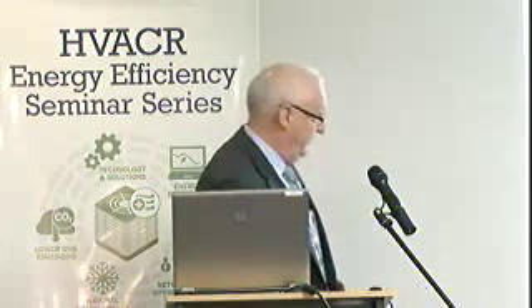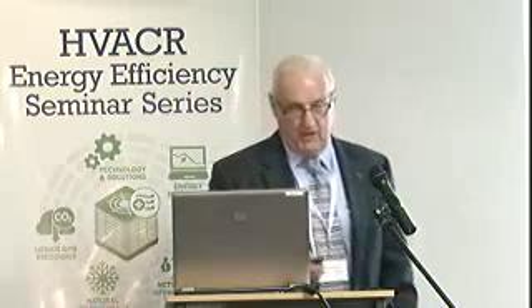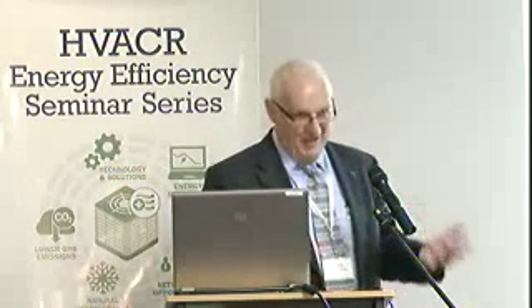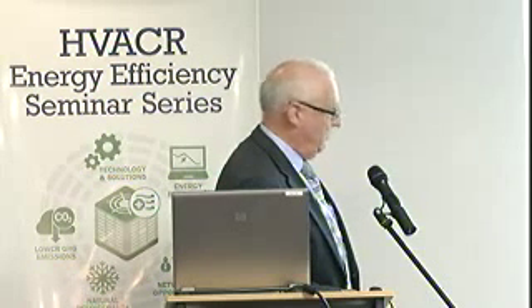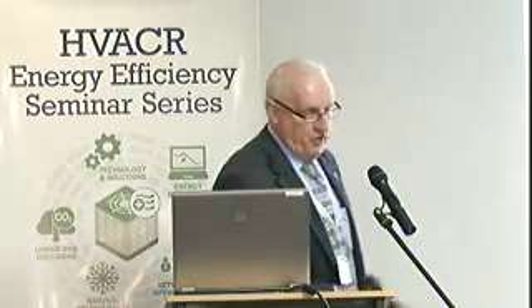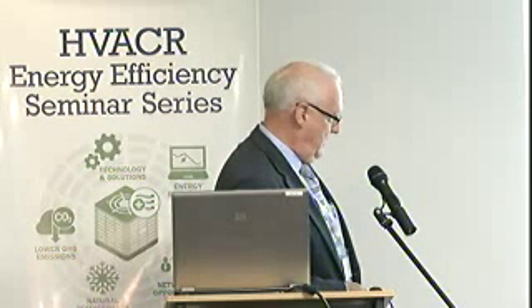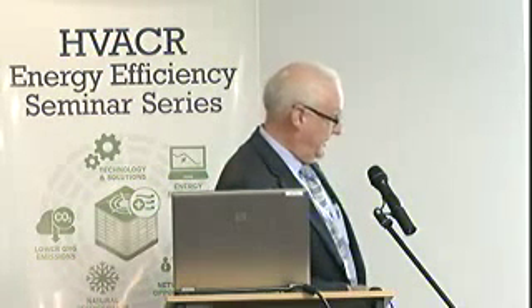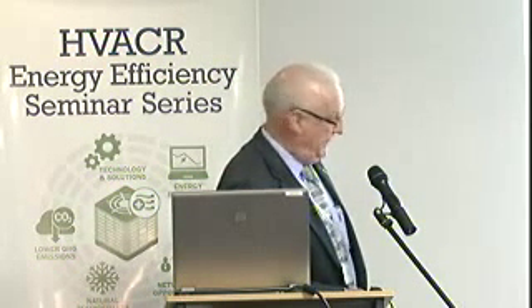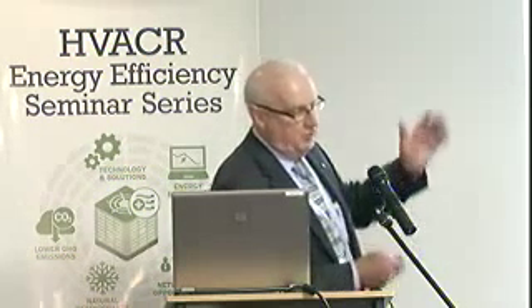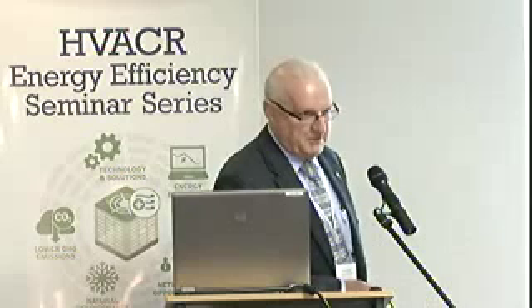Very quickly, the difference between power factor correction and VPO, and this is relatively high level layman's term type stuff. We all know AC power is a sine wave. I've shown two sine waves here, one for voltage, one for current. And this is for a site that's got, and I haven't tried to quantify these numbers for you, an out of synchronisation, we'll call it, between the current and the voltage waveform with poor power factor. And power factor is effectively the difference between those two. It's not vectorially, but for the purposes of this, that's what it is.